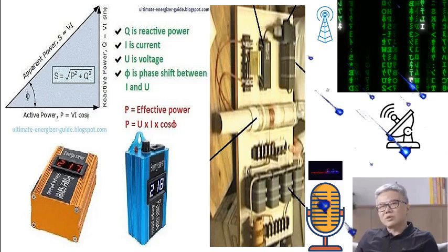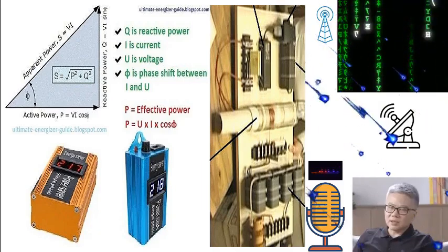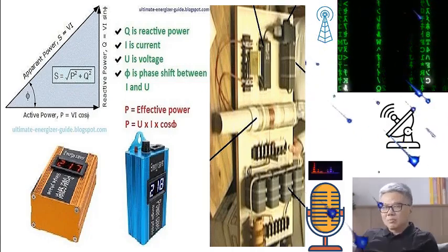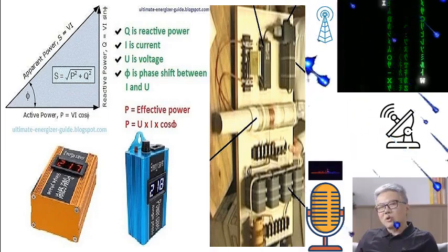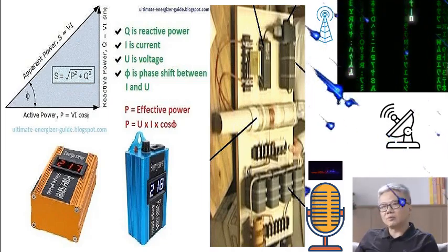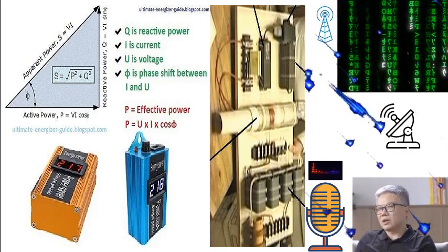Methods for improving the natural cosφ factor. One of the primary methods for reducing reactive power is improving the natural cosφ factor. This approach involves optimizing the operational efficiency of electrical equipment so that less reactive power is needed from the power source. The following measures are common for enhancing the natural cosφ factor. Technological process optimization. Electrical equipment must operate in the most efficient mode. This may involve adjusting processes or redesigning systems to better utilize electrical power and reduce the reactive load.